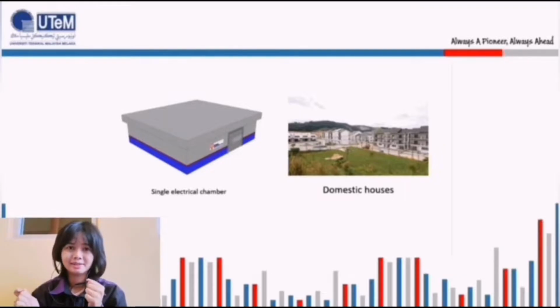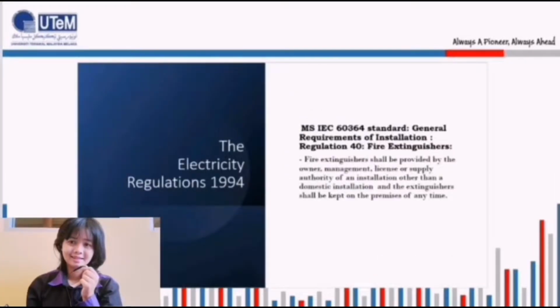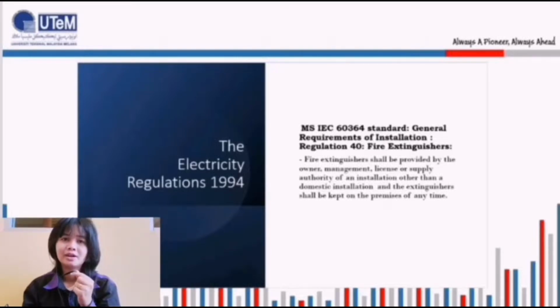It can apply to domestic housing, and the regulation common to the single electrical chamber and domestic housing is the Electricity Regulations 1994. This law is under Part 2 of the regulations, which is Installation, and under the general requirements of installation, MS IEC 60364 standard, it states the regulation for fire extinguishers. This law states fire extinguishers shall be provided by the owner, management, licensee or supply authority of an installation other than a domestic installation, and the extinguishers shall be kept on the premises at all times.